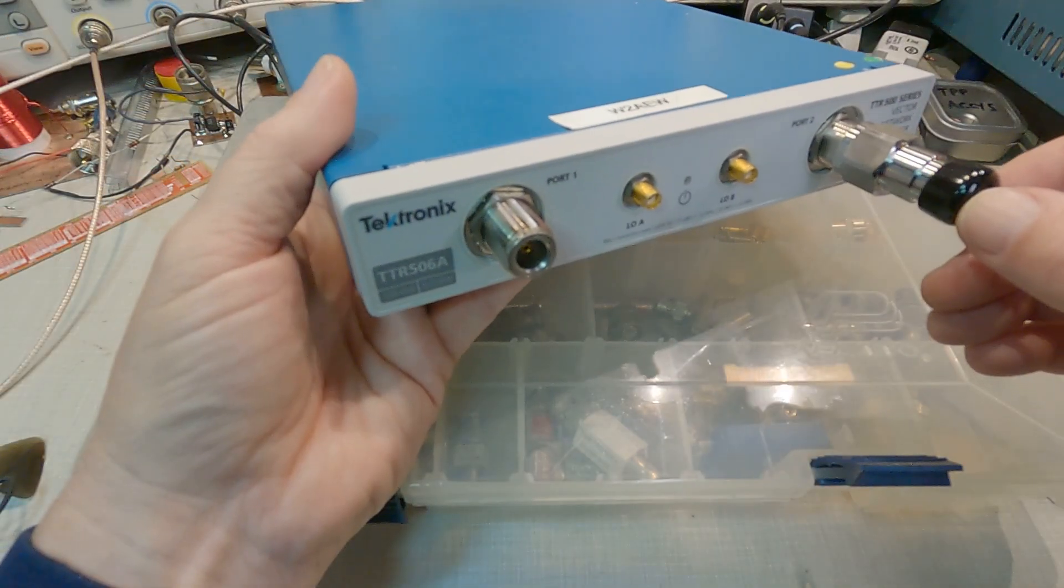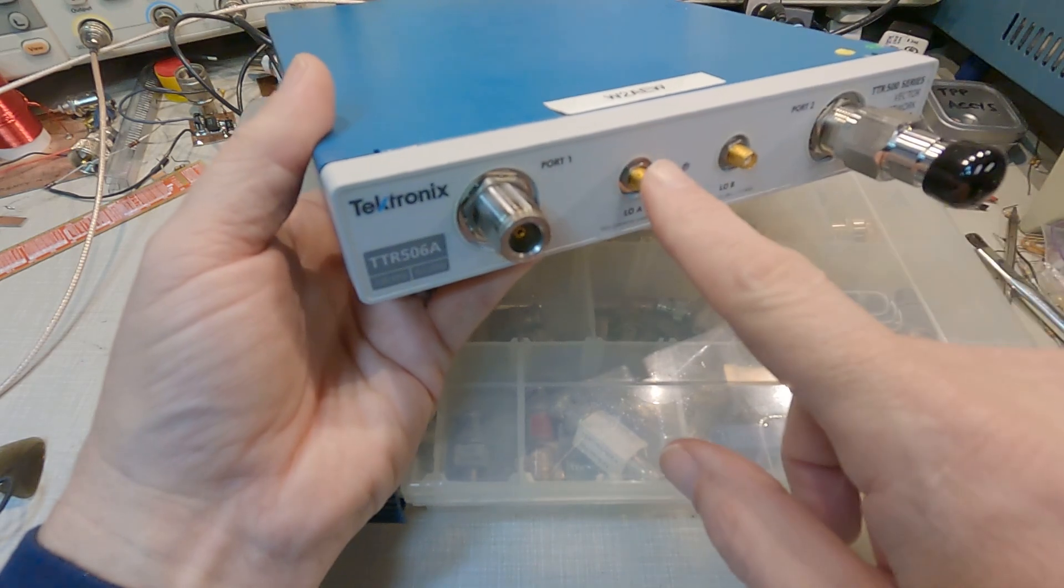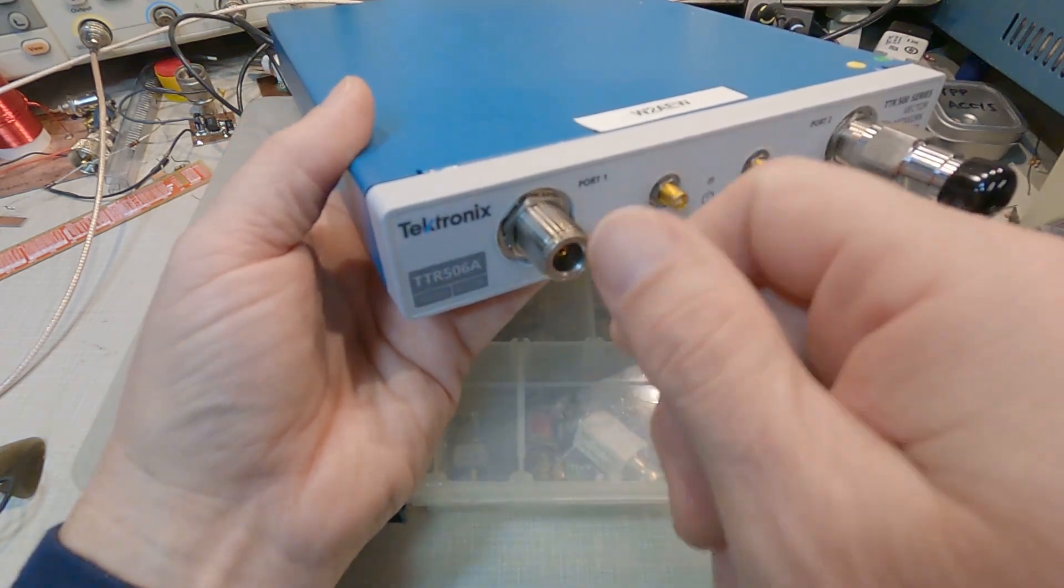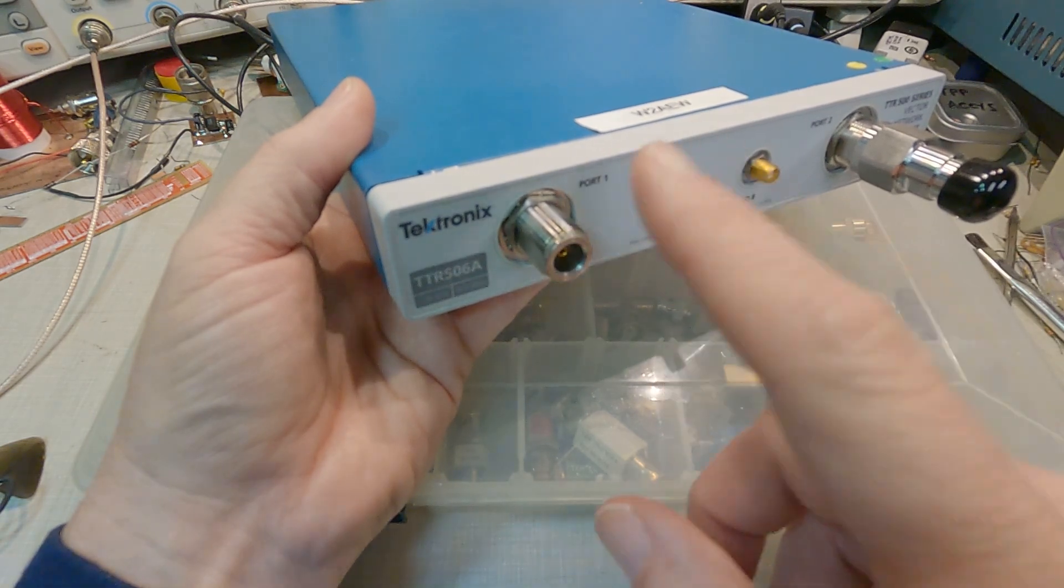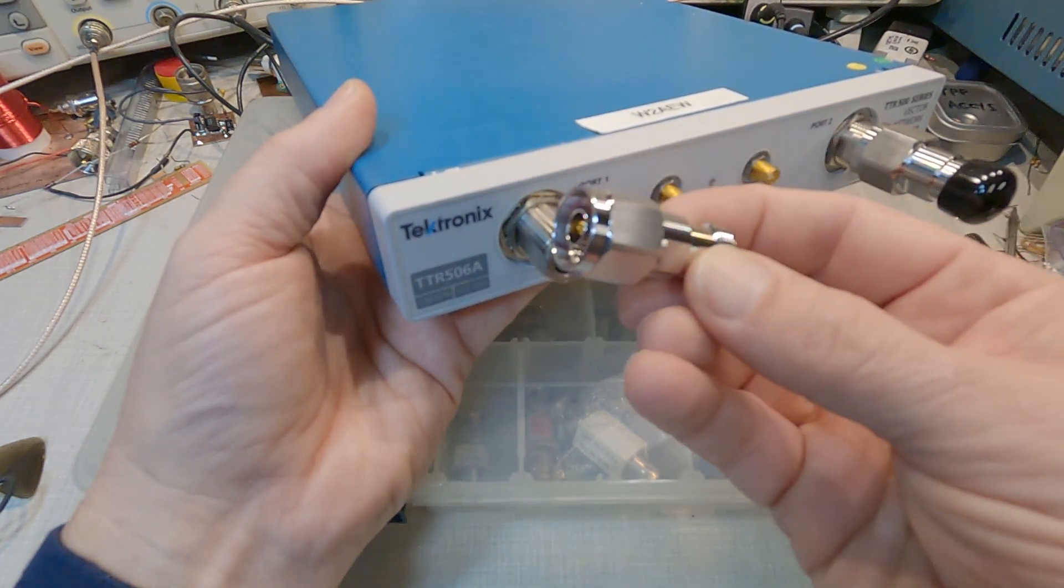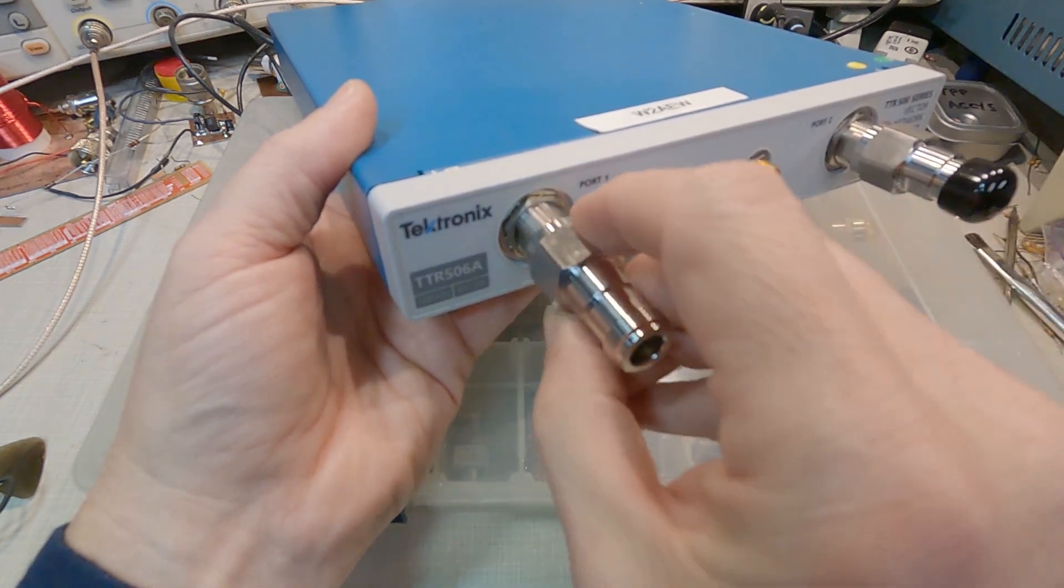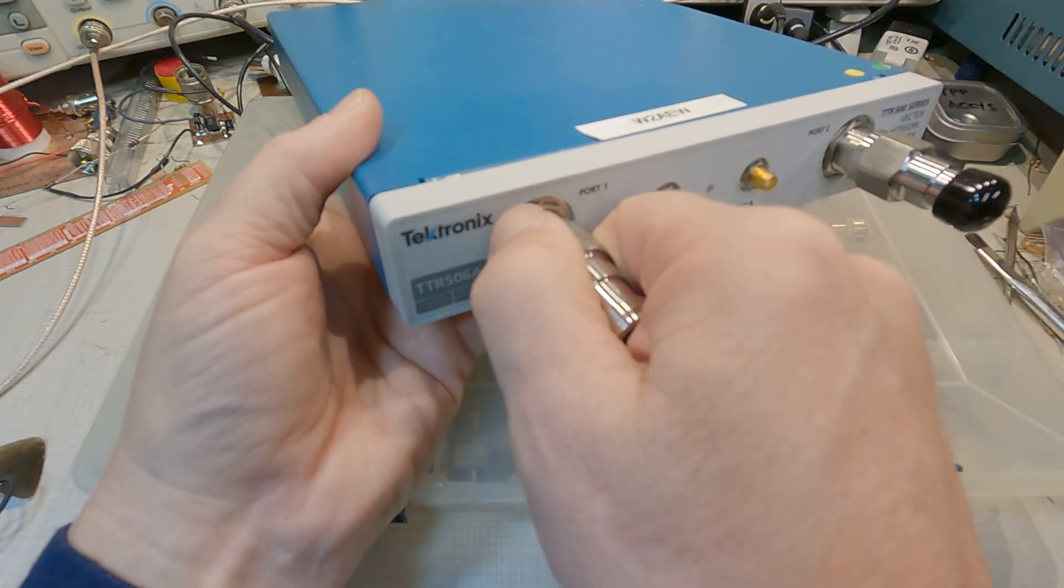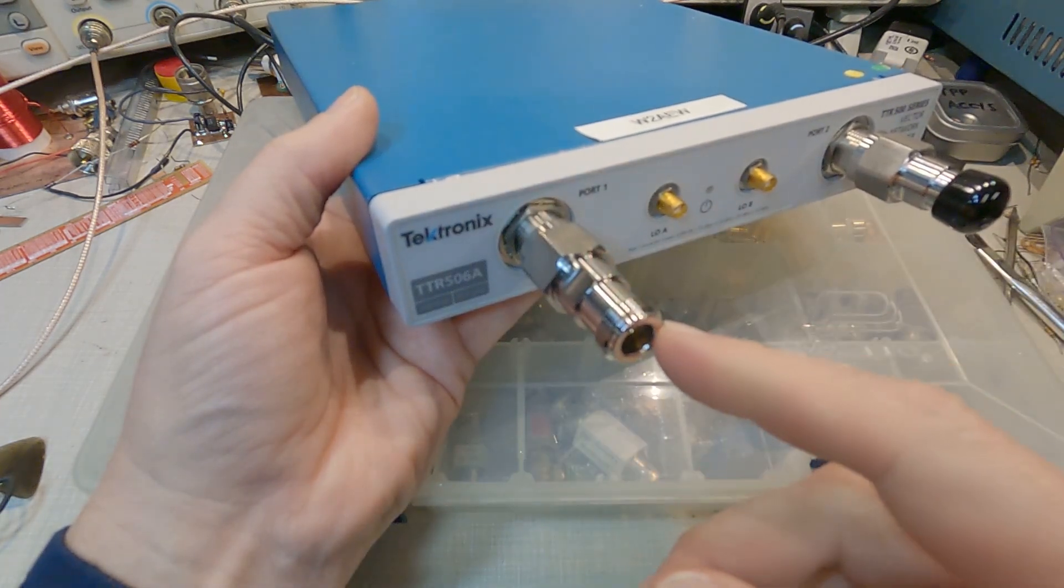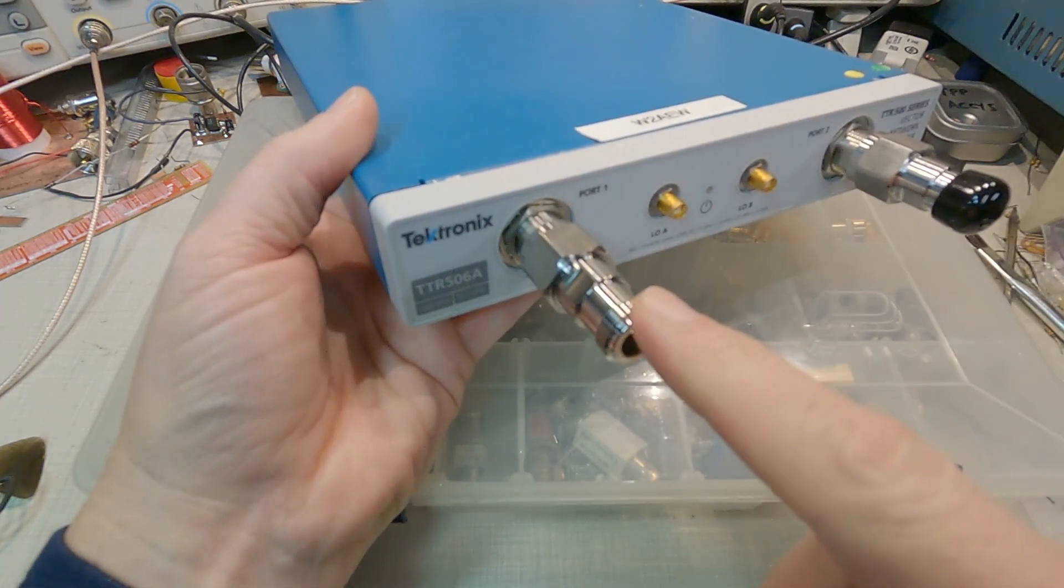Now if you've got an expensive piece of RF test equipment, such as this vector network analyzer, where you make a lot of connections and disconnections when you're doing things like calibrations and measurements, it makes sense to use connector savers.